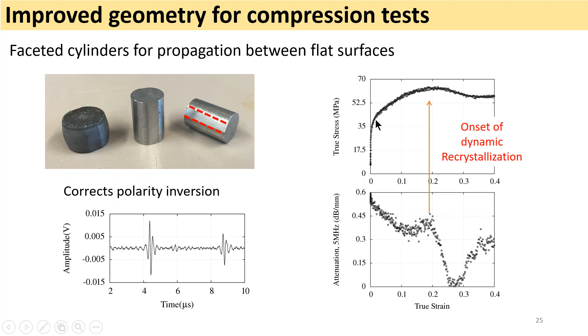Here in this figure, we can see a typical stress-strain curve where the stress increases as the strain increases, up until a moment where we see a decrease in the flow stress, corresponding to the moment where dynamic recrystallization starts to begin. What I have tried to do is take those waveforms, analyze the attenuation and plot it as a function of strain, to see if there would be some correspondence between the moment where we see a decrease in flow stress and the attenuation signal. What you can see here is that there is indeed a sharp decrease in the attenuation signal, which is for now very hard to interpret in terms of microstructure properties, but at least it gives you an indication that this type of machine can actually tell you the moment where dynamic recrystallization occurs.